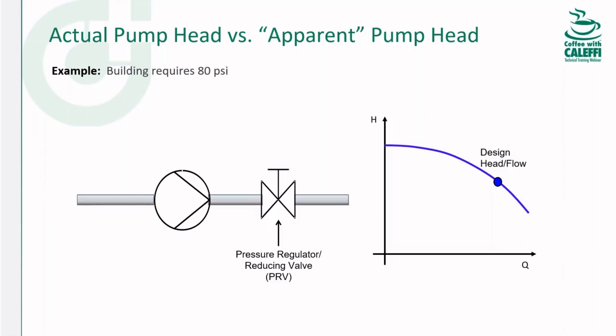It's especially important for retrofit applications. I call it actual pump head or actual pressure versus apparent pump head or apparent pressure. So when you're especially replacing existing systems with pressure regulator valves, like the one you saw on the previous slide, here you've got a pump curve with a design head and flow, which we're rarely going to run at for a booster. And then what we're doing today is supplying variable speed systems. So you're going to have what we call a constant pressure control curve typically, and that represents a straight line. As you reduce flow, you're going to follow that control curve and keep the pressure constant on the discharge supplying the building.